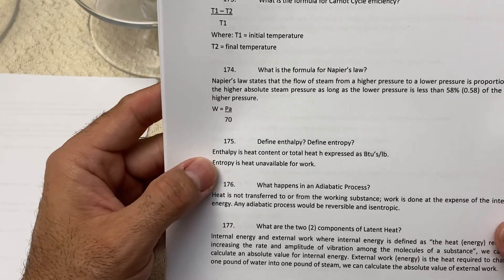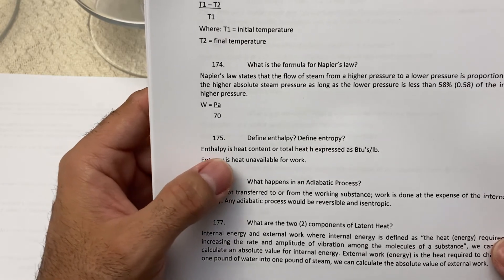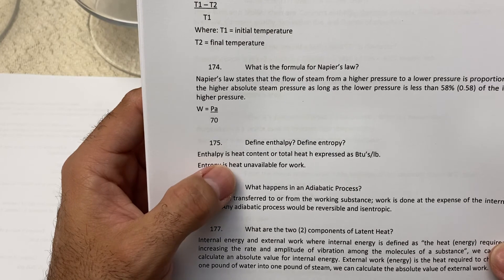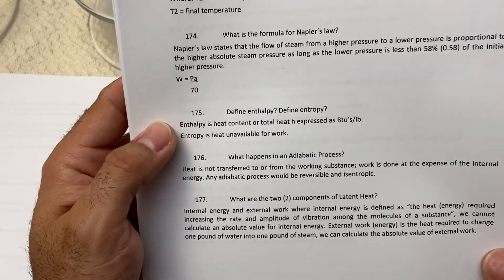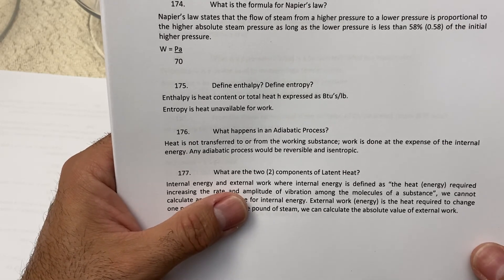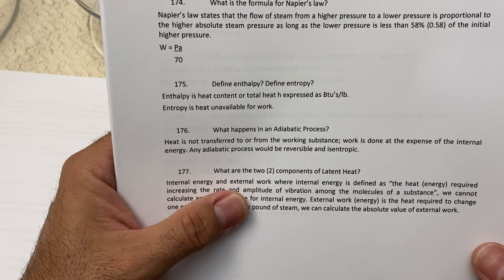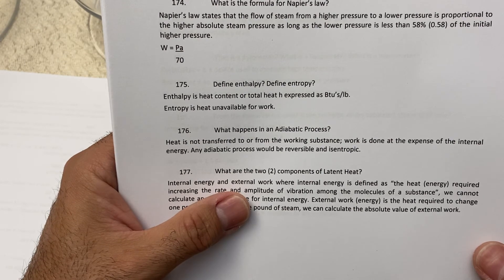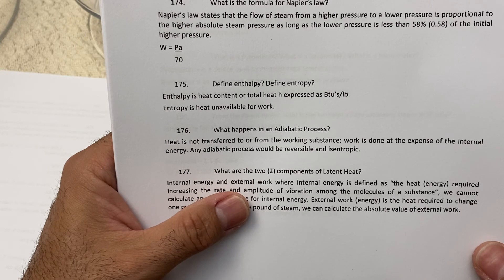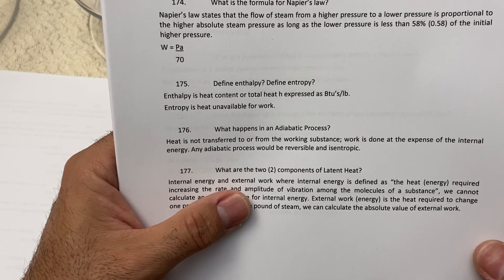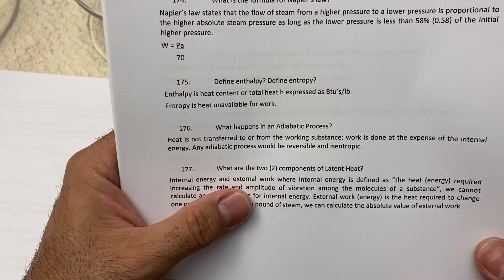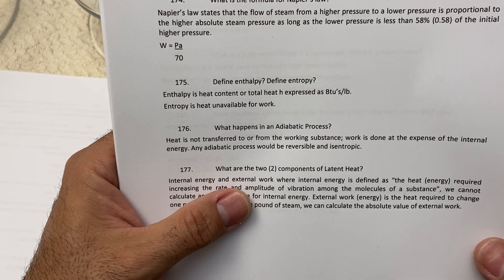Also important for beginners: enthalpy is heat expressed in BTUs per pound. You also need to know the definition of latent heat — heat added to a substance that changes the state of the substance without changing its temperature. The latent heat for water to become steam is 970.3 BTUs, and the latent heat for one pound of ice to become one pound of water is 144 BTUs.